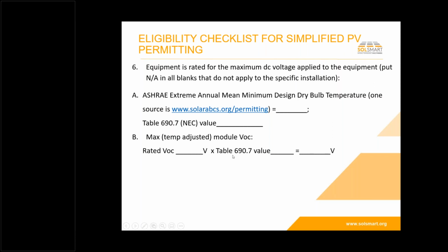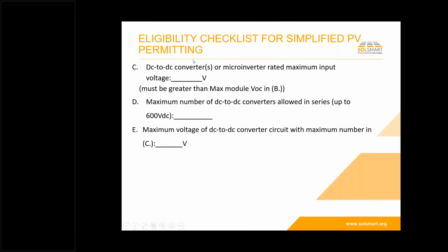We stick that in there, and let me get back to this slide. And that's just to explain, we might have a rated voltage of, let's say, 45 volts, and then we take that 1.18 or whatever it was for your area, and then you come up with the voltage, and you determine whether or not that is within the ratings of the equipment. Okay, we could have a DC to DC converter that has a maximum voltage rating. That voltage rating could be 60, 70, 80 volts, something like that. And then we could have the maximum number of DC converters that are allowed in series. And so if we're using DC converters, then we put that in. If not, obviously, we either just don't fill it in or put NA.